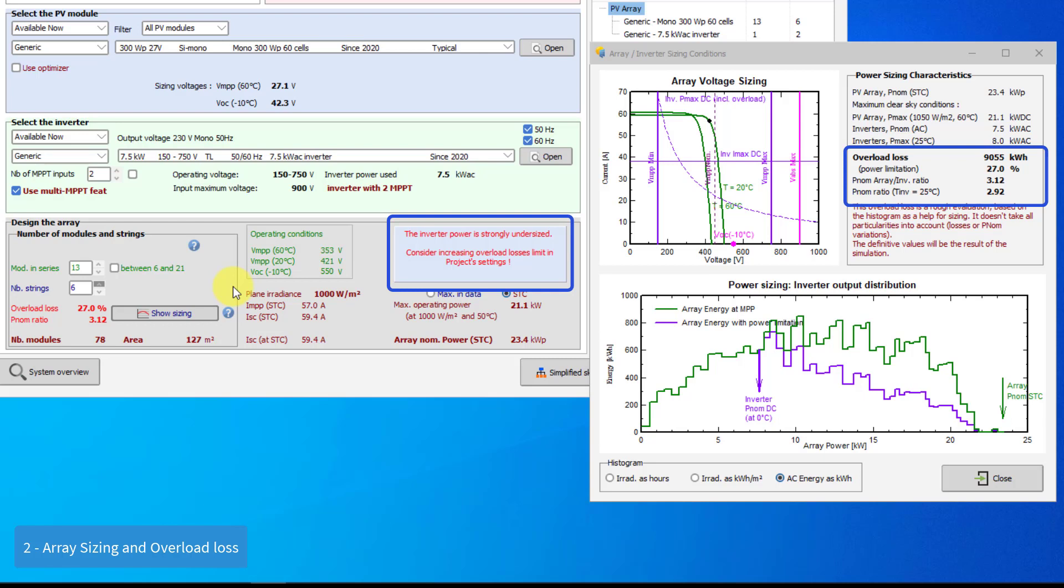When the overload loss is between 0.1% and 3%, PVSYST considers a slightly undersized inverter and puts an orange warning. However, if the overload loss exceeds 3%, PVSYST gives an error message in red and then the simulation will not be possible. If you want to create systems with a highly oversized PV array, you can increase the limit of 3% in the project's settings.